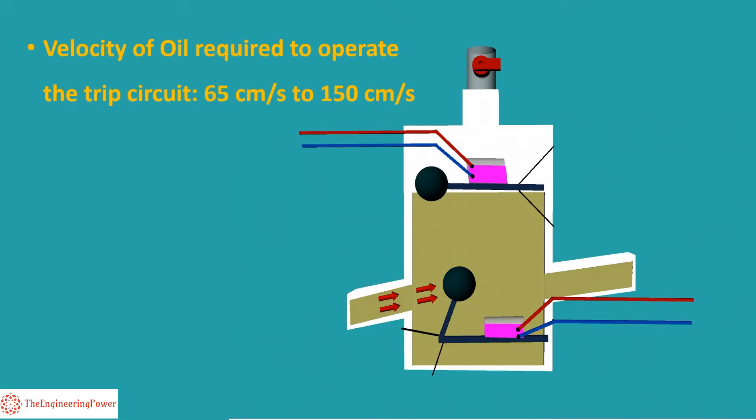The velocity of oil required to operate the trip circuit of relay varies from 65 cm per second to 150 cm per second depending upon the size of the relay and rating of the transformer.